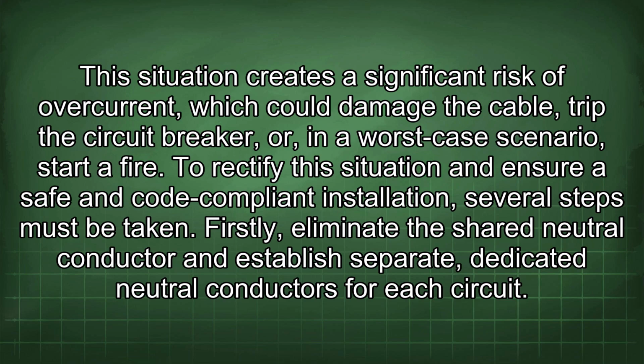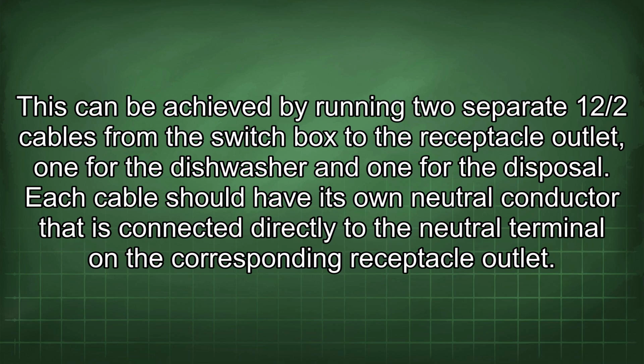To rectify the situation and ensure a safe and code-compliant installation, several steps must be taken. Firstly, eliminate the shared neutral conductor and establish separate, dedicated neutral conductors for each circuit. This can be achieved by running two separate 12/2 cables from the switch box to the receptacle outlet, one for the dishwasher and one for the disposal.